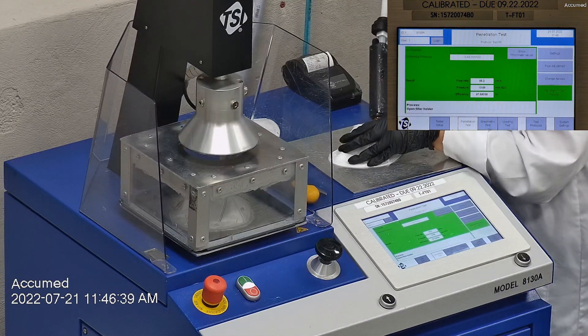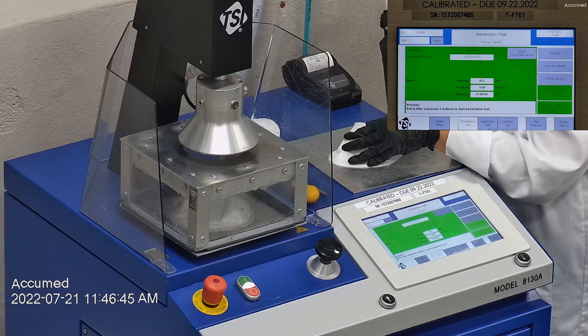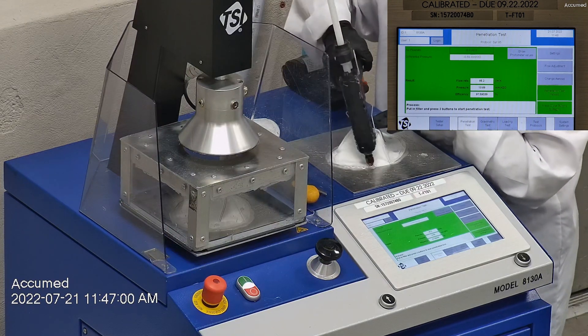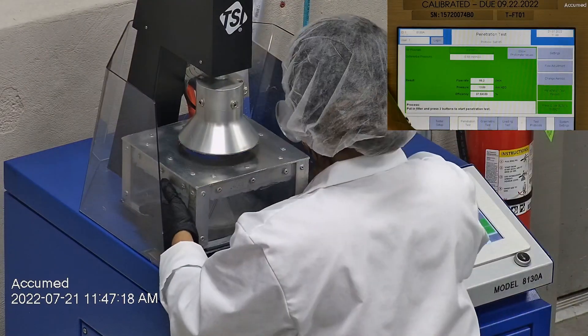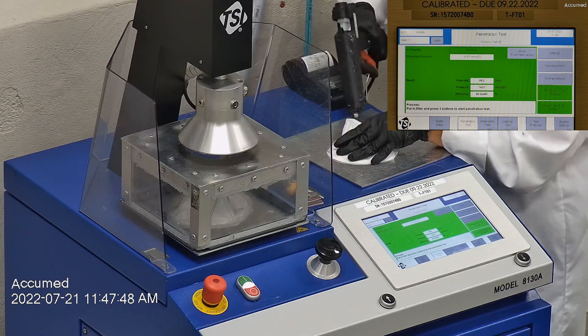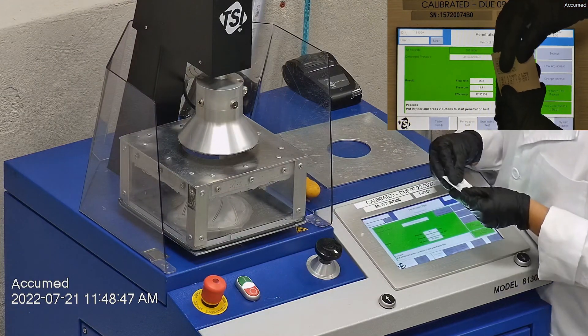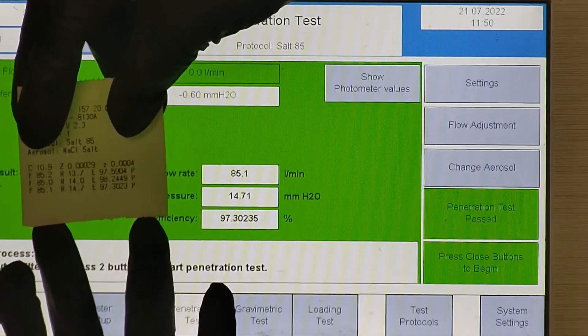The first sample tested at 97.56% filtration efficiency with a pressure drop of 13.7 millimeters of water. The second sample had a filtration percentage of 98.24% and a pressure drop of 14 millimeters of water. The last sample's filtration percentage was 97.30% and had a pressure drop of 14.7 millimeters of water.